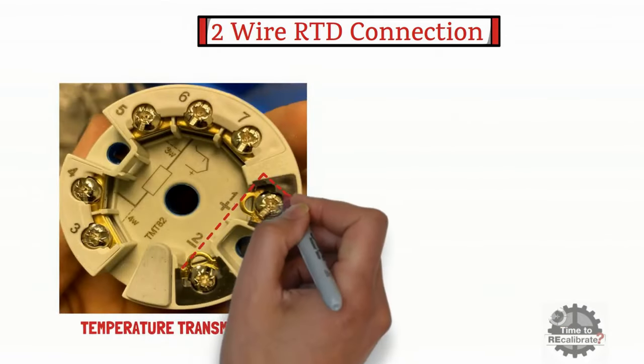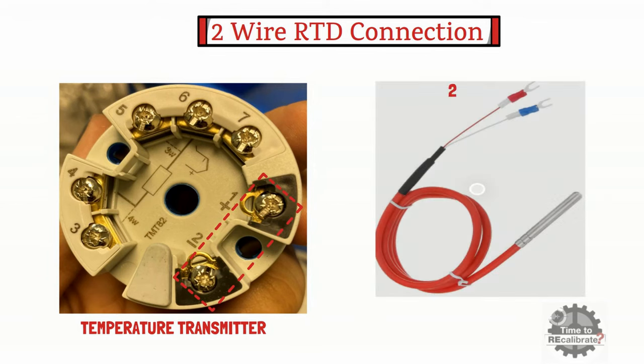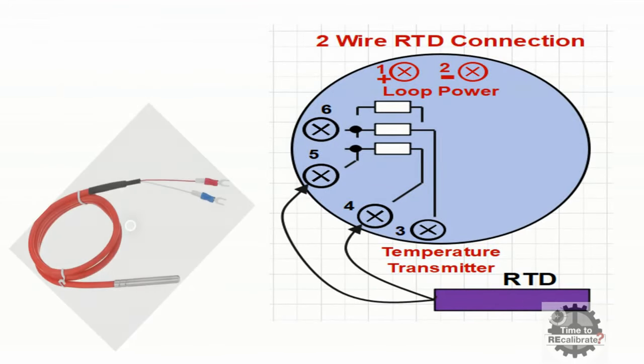The loop power supply will be connected to terminal number 1 and terminal number 2, and terminals 3, 4, 5, and 6 are used for RTD sensor input. As the name suggests, a 2-wire transmitter has 2 cables — one red and one white. To connect 2-wire RTD to the temperature transmitter, connect the red cable to terminal number 5 and connect the white cable to terminal number 4 of the temperature transmitter.